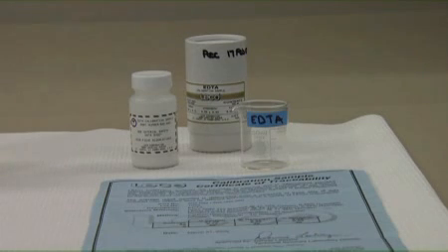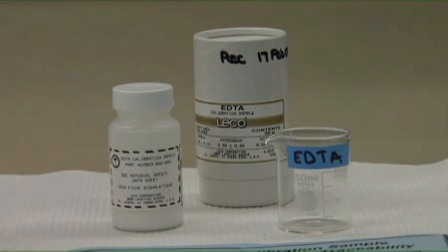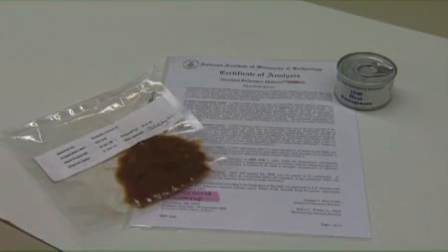For a standard, use the EDTA calibration sample supplied by LECO, calibrated and traceable with a minimum purity of 99%. The EDTA standard must be recalibrated annually, or a new standard must be ordered unless the nitrogen result remains within plus or minus 1% of the manufacturer's reported value. The use of a control sample or a standard reference material is strongly recommended.